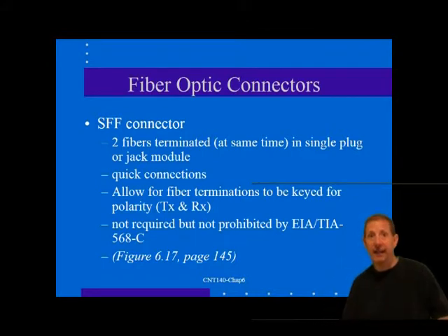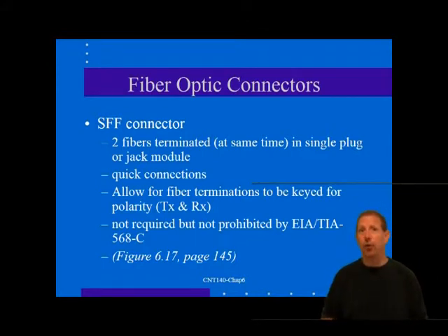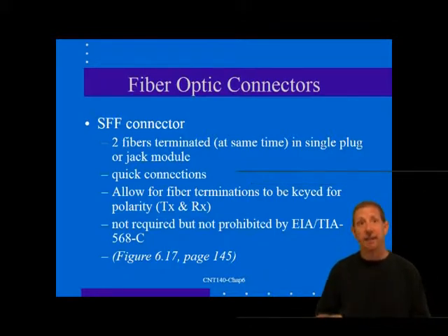The SFF connectors were first authorized as part of a general deregulation of fiber connectors in the -B revision, which is continued in the TIA 568, specifically the 568C.3 Optical Fiber Cabling Component Standard.